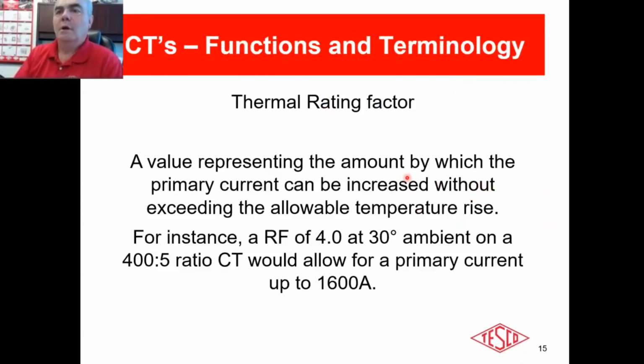All right, so that's our thermal rating factor. Now, when we talk about a thermal rating factor, there is an ambient, and that's in degrees C. All right, so there is an ambient, which is our standard temperature. So does this thermal rating factor change if it's colder? Yes. If it's colder, it will change a little bit. If it's hotter, it will change a little bit. This theoretically could go up a little bit or down a little bit. But for all intents and purposes, with a thermal rating factor of 4.0, I can take this 400 to 5 CT and I can bring it up to 1600 amps. Okay.